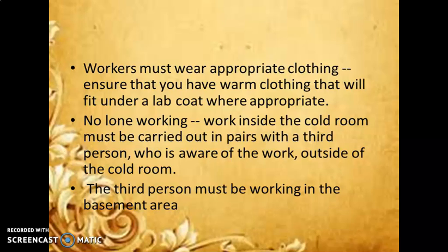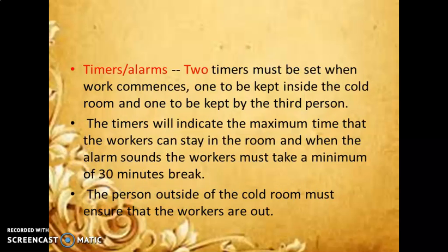Work inside the cold room must be carried out in pairs, with a third person who is aware of the work outside of the cold room. The third person must be working in the basement area. Timers or alarms. Two timers must be set when the work commences, one to be kept inside the cold room and one to be kept by the third person. The timers will indicate the maximum time that the workers can stay in the cold room, and when the alarm sounds, the workers must take a minimum of 30 minutes break. The person outside of the cold room must ensure that the workers are out.